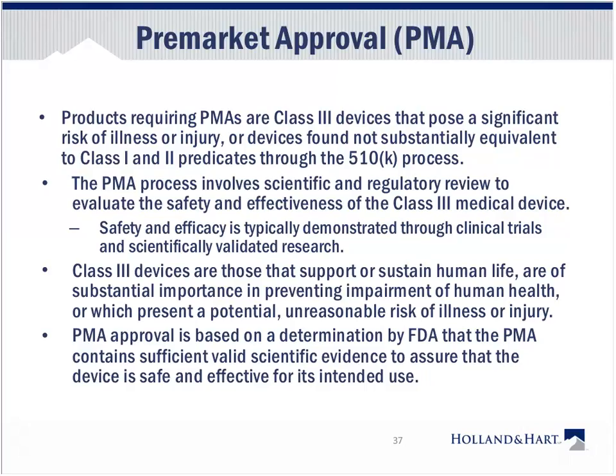Products requiring pre-market approval, these Class 3 devices, are the ones that pose significant risk of illness or injury, or devices found not substantially equivalent to Class 1 and Class 2 predicate devices through the 510K. So if you have a device that is not exempt from pre-market notification and you can't get it through pre-market notification any other way, by being substantially equivalent or grandfathered in, then you have to go through the pre-market approval process. Again, expensive, time-consuming, and it requires validated research. The PMA process involves scientific and regulatory review to evaluate the safety and effectiveness of a Class 3 medical device. Safety and efficacy is typically demonstrated through clinical trials and scientifically validated research.